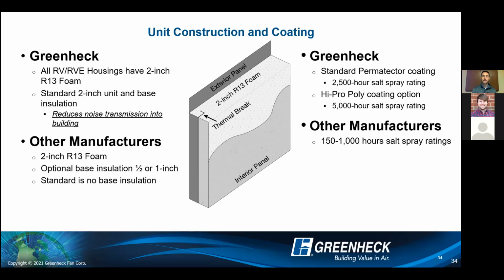It does reduce that noise, like I said, especially with digital scroll type compressors, if you've ever heard those noise concerns, because we have that 2-inch R13 base and we have the compressors elevated on an elevated shelf in an insulated cabinet, so you definitely don't get that concern from a noise standpoint either. Other manufacturers, what you're seeing is, again, 2-inch R13 foam, more so foam boards. But from a base insulation standpoint, standardly, they're not going to offer base insulation. And then if they do, you're generally going to see a 1/2 inch or maybe up to 1 inch of that base insulation. So just keep in mind that we have that 2-inch base insulation as well.